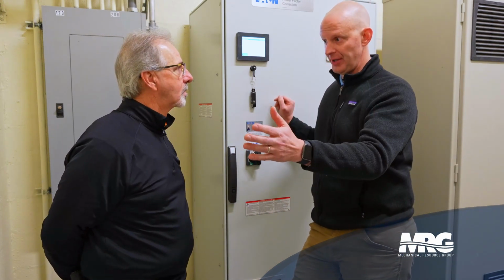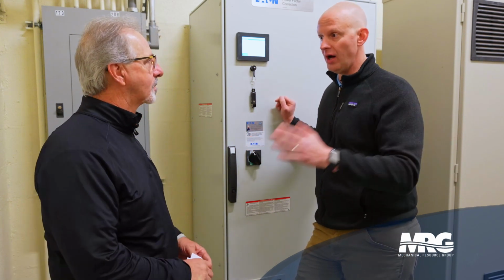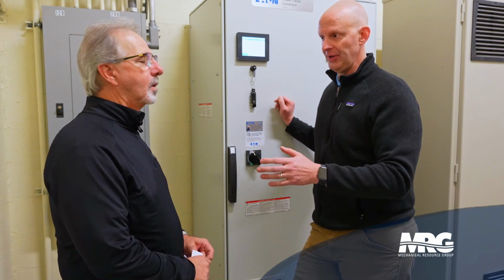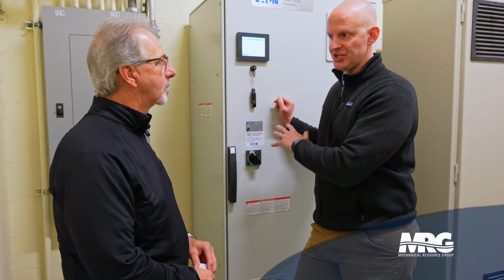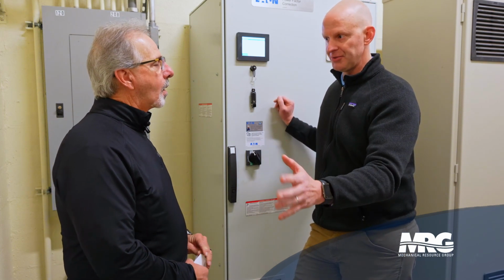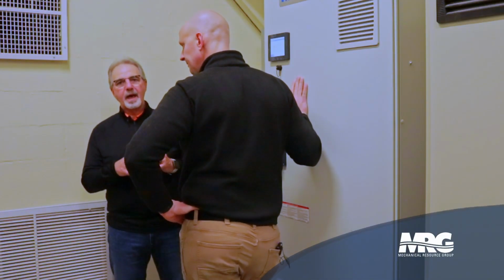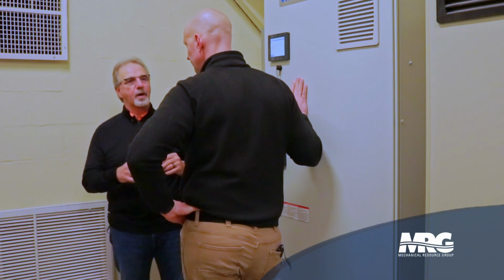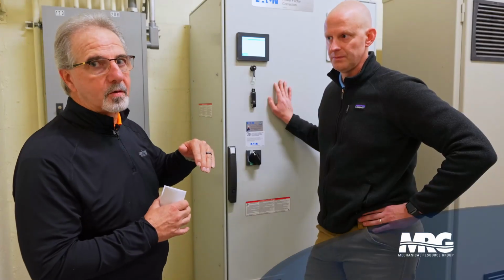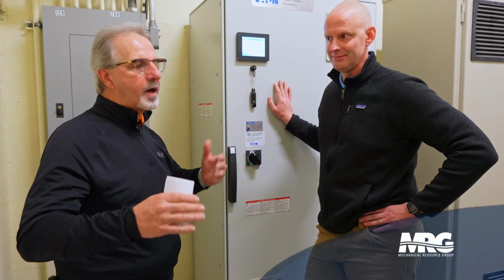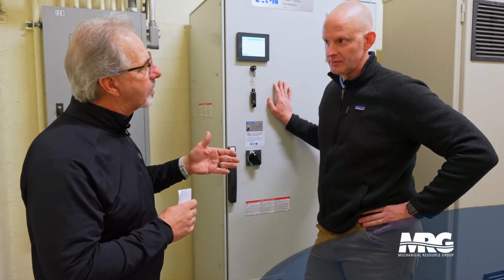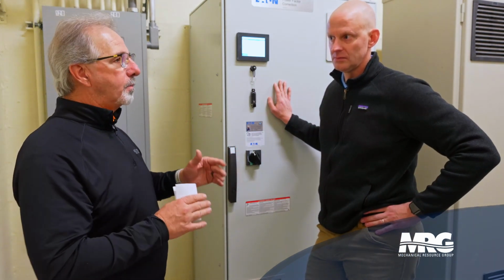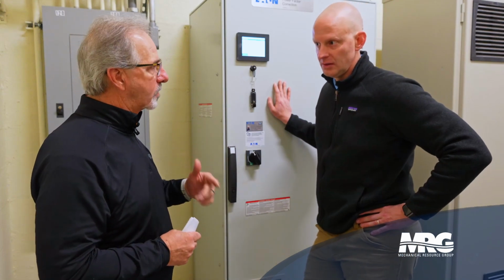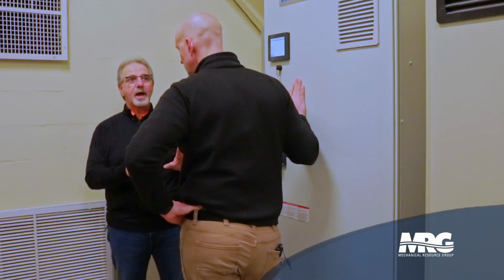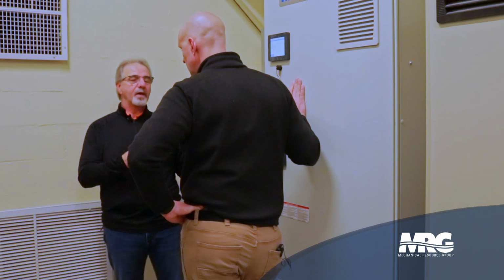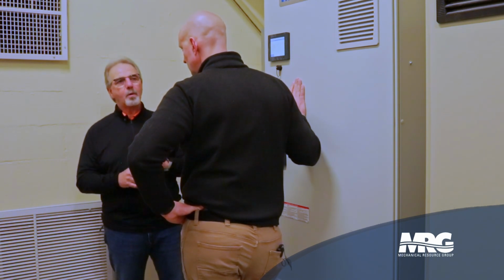We also have a giant diesel generator in the back. Yes. So this place is designed to run throughout any kind of significant event, any kind of power failure and such. But how do harmonics and managing that and a huge generator all come into play? I'm sure it makes things more complicated. Well, it makes things more complicated because when you're dealing with an active filter or a low harmonic drive, whichever one, you have multiple zero crossings. The generator is counting those zero crossings to try to sync up its waveform, so it makes it hard for it to move into functionality because you have so many zero crossings. So it's a timing sequence that we had to set up in the generator. And we had to set it up in case all 3 pumps were running, because in the event that we did lose power, we don't want to leave people without water.